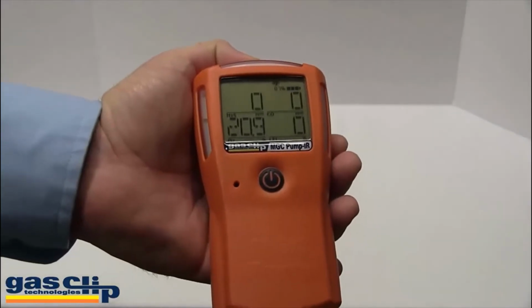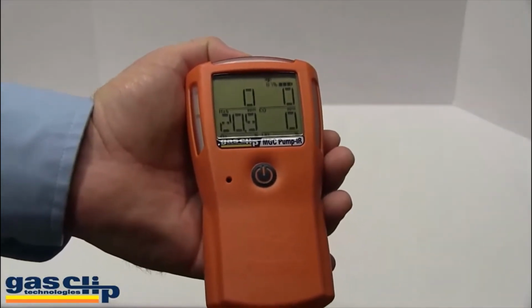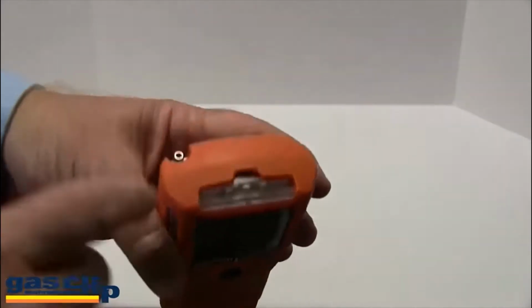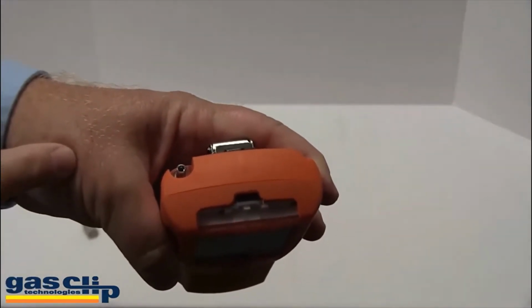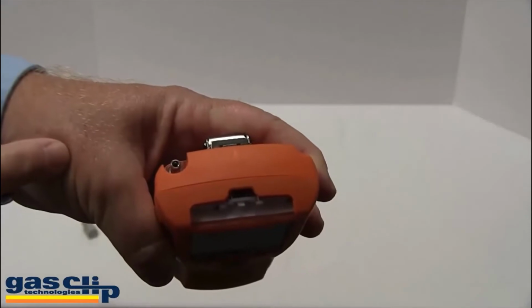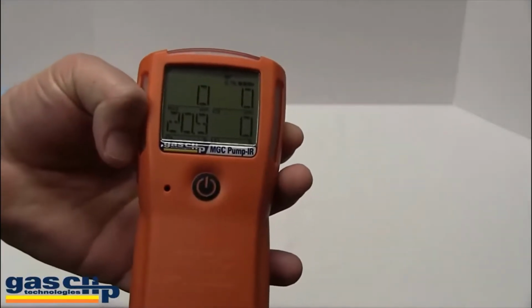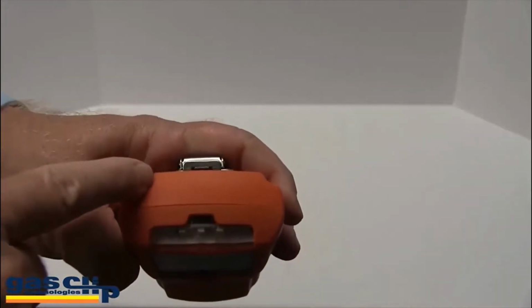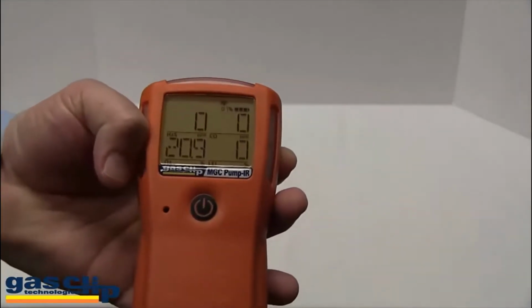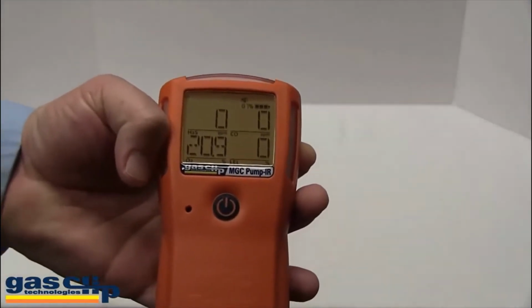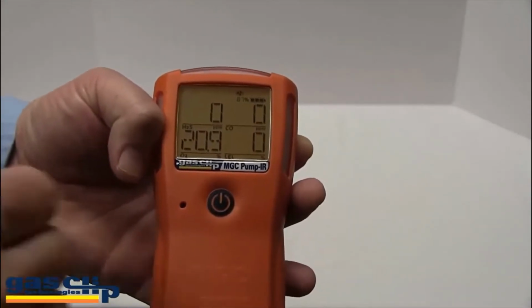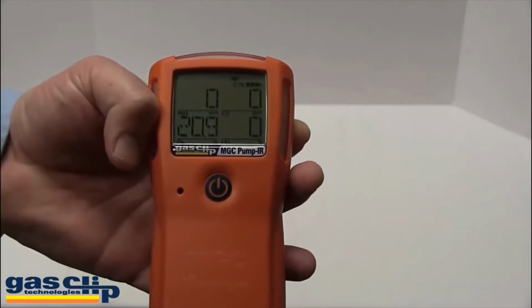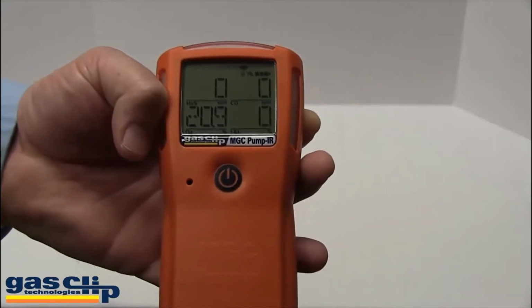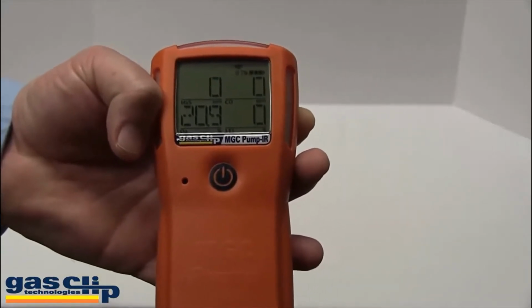Also notice that we do have a pump block feature built into the pump. To test this, all you have to do is place your finger over the opening and the monitor will go into alarm. To remove the alarm, all you will have to do is press the power button. What that allows you to do, if any water is brought up into the hose, it will automatically stop the pump motor, keeping the water from going into the pump and destroying the monitor itself.